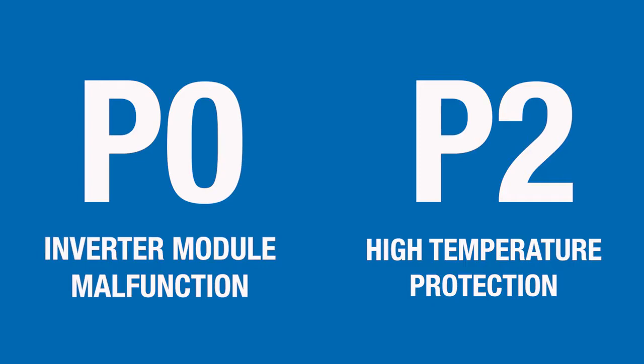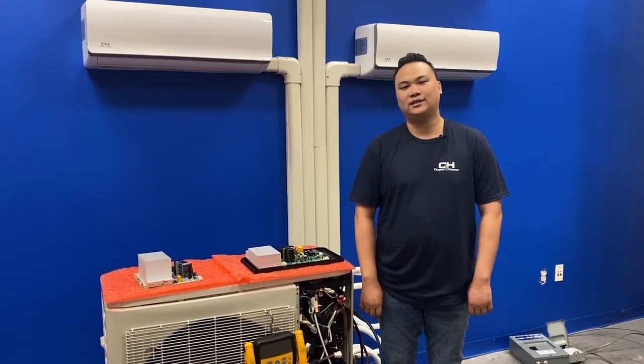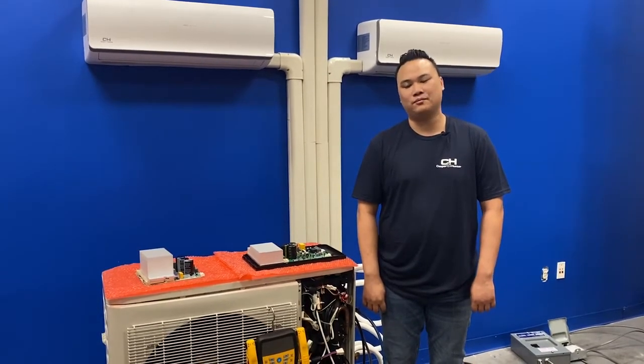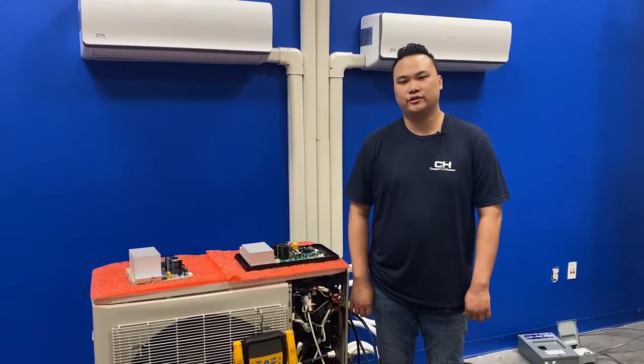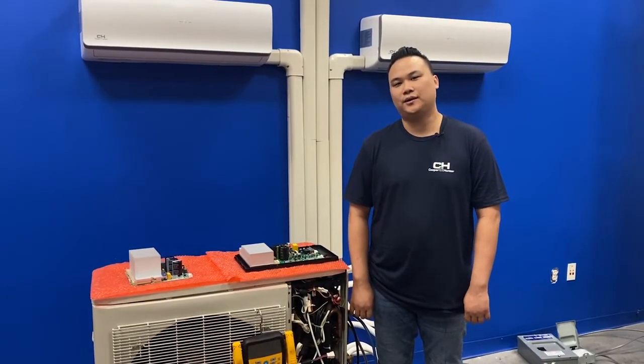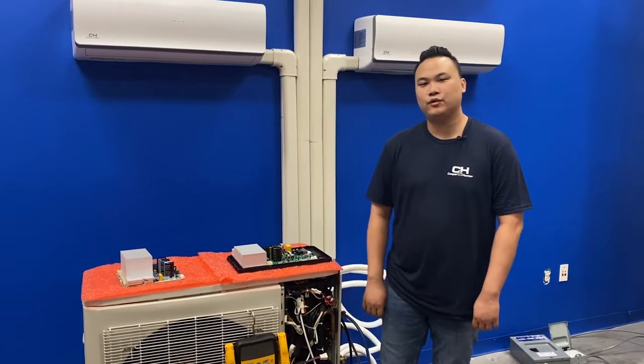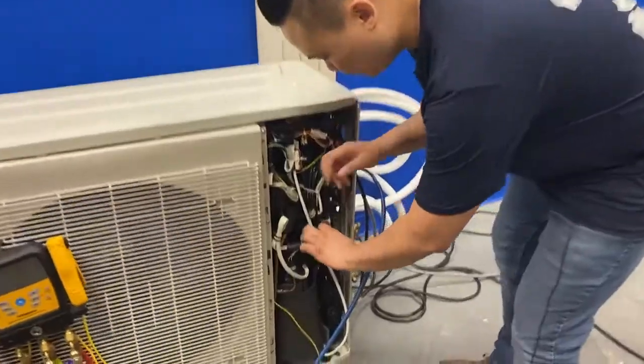If your indoor unit is displaying a P0 or P2 error code, that indicates an inverter module malfunction or high temperature of compressor top or IPM board. This could mean one of 2 things. Either you have a short on your IPM board, or your pressures are too high or too low. First, we're going to check pressures on the unit to make sure they're not too high or too low. Then we're going to check the IPM board.